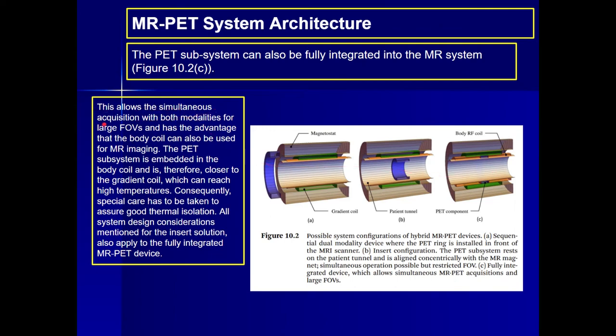This allows simultaneous acquisitions of both modalities for large FOVs and has the advantage that the body coil can also be used for MR imaging. The PET subsystem is embedded in the body coil and is therefore closer to the gradient coil, which can reach higher temperatures. Consequently, special care has to be taken to ensure good thermal isolation. All system design considerations mentioned for the insert solutions must also apply to the fully integrated MR-PET device.